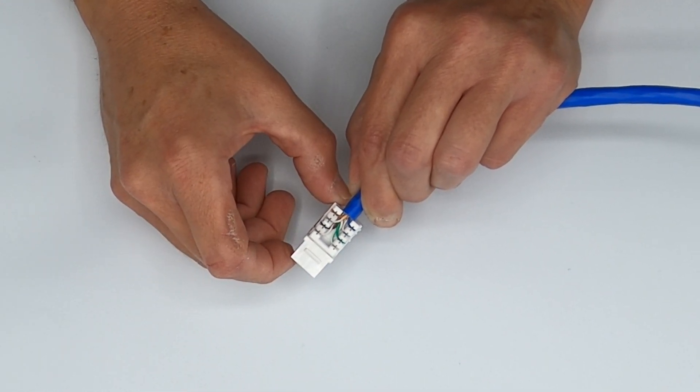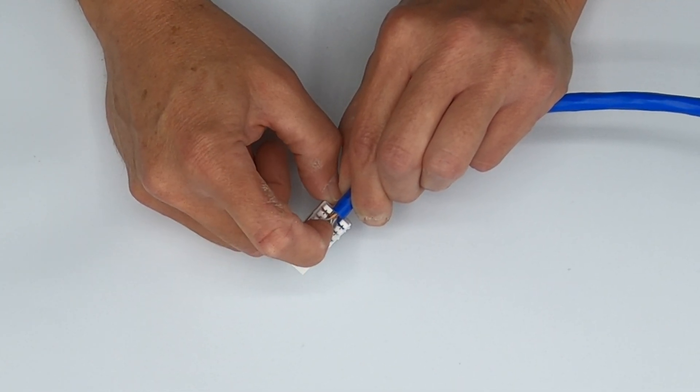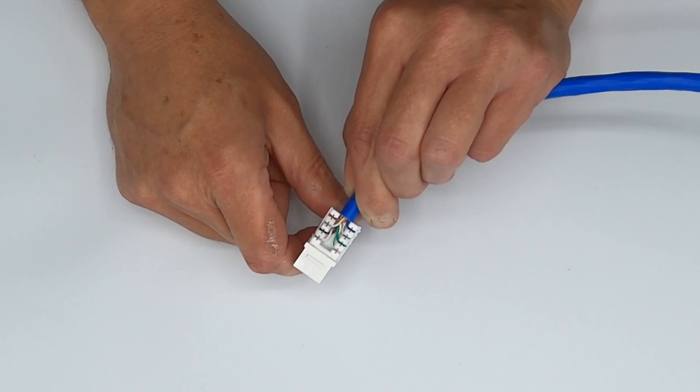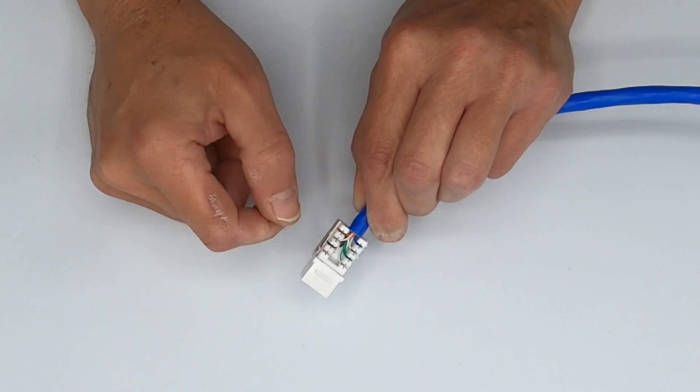If you notice the conductors from the - if you look at the conductor pairs, where the untwist stops or where the twist stops and it gets untwisted in order to get into these slots is no more than one half inch. And this jack will perform exactly like it should.